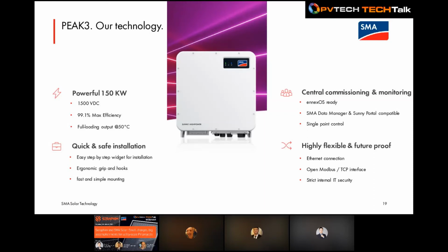The special thing about this one is not just that it only has one MPPT. The DC input is actually 1,500 volts. As you may know, in large scale nowadays, we are trying to push for the 1,500 volts design, as it actually can save a lot of upfront costs. And that is the future, the trend that it will be. The inverter has 99.1 percent maximum efficiency, and the full loading output all the way up to 50 degrees Celsius.